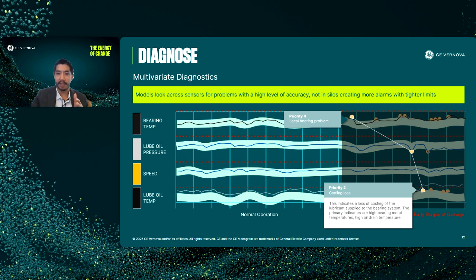But as time progresses, the asset degradation might continue. SmartSignal starts to see and correlate deviations between this bearing metal temperature and the lube oil drain temperature and vibration levels. What you're seeing next then is a priority 3 cooling loss issue advisory.